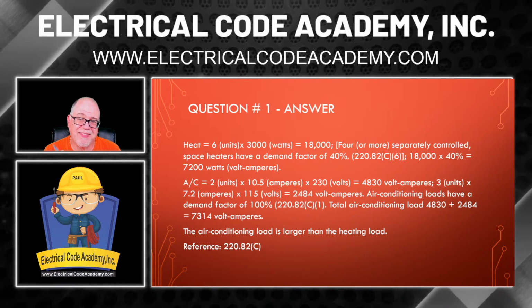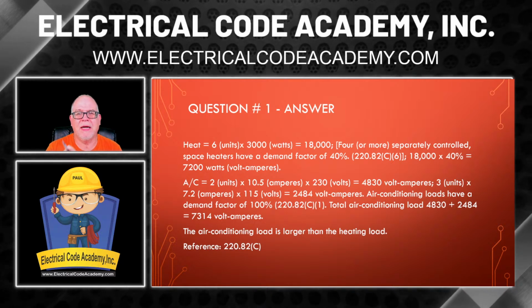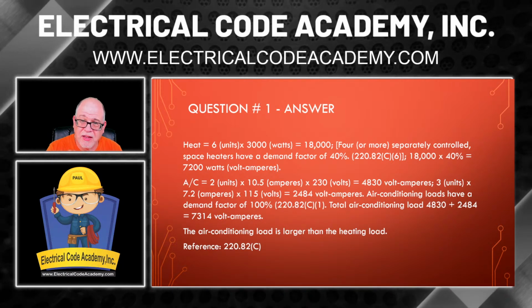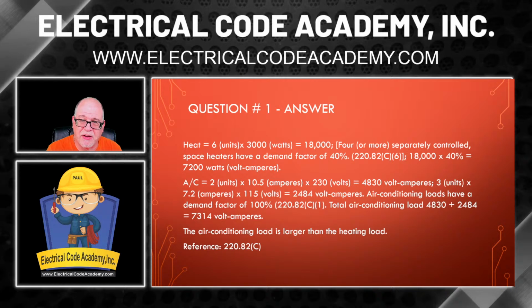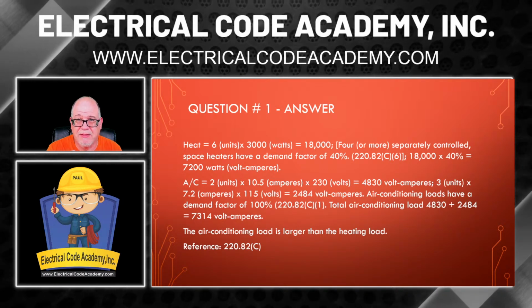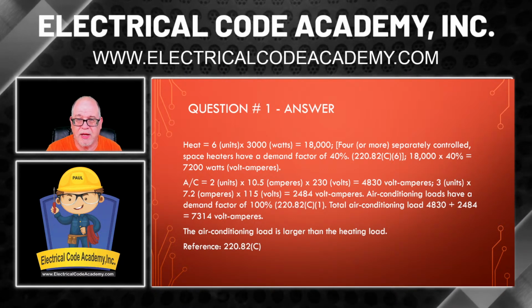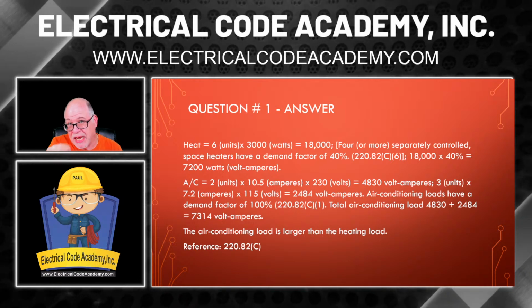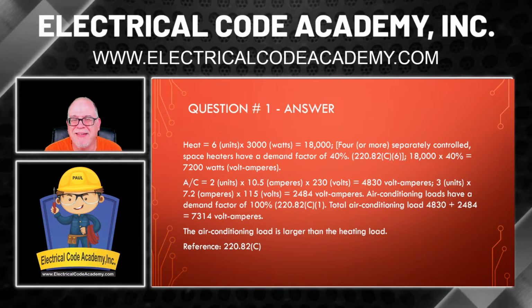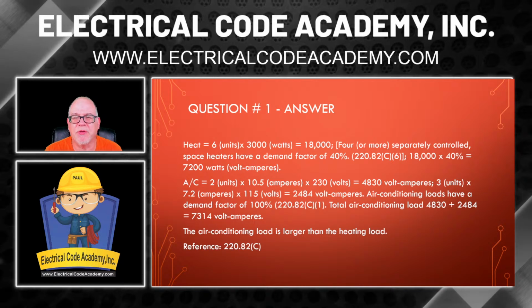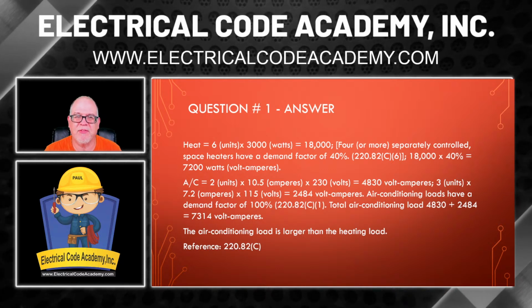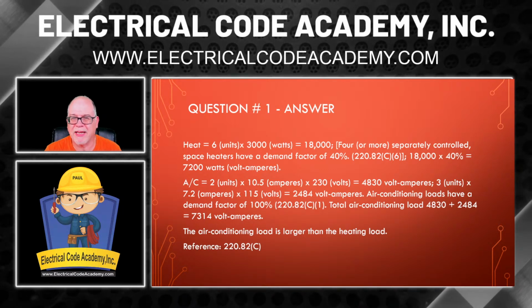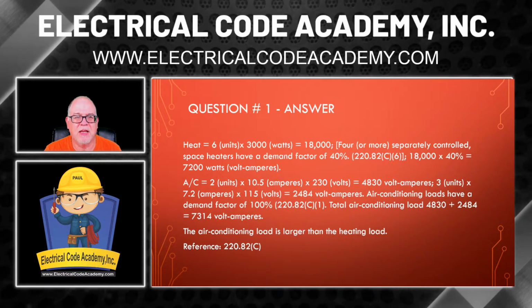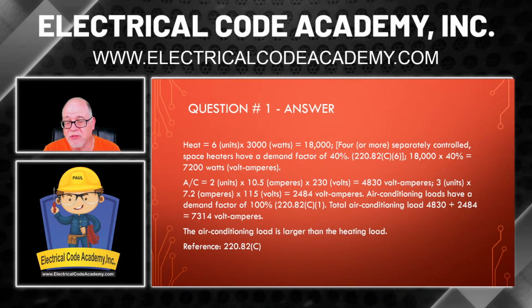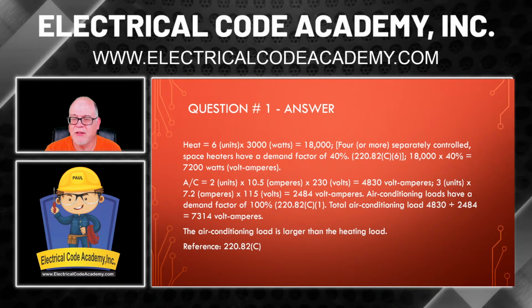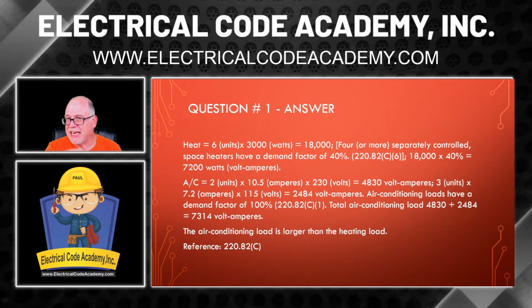Now, remember what it said? It says that we take what? Now, this says 220.82(C)(6), but it's actually, which one was it? It was (5) that we're using for the heat. So typo. We're doing 18,000, and we're going to multiply that by 40%. That gives us 7.2 kW, or in our case, since we worked it out in watts, it is 7,200 watts, or 7,200 VA.